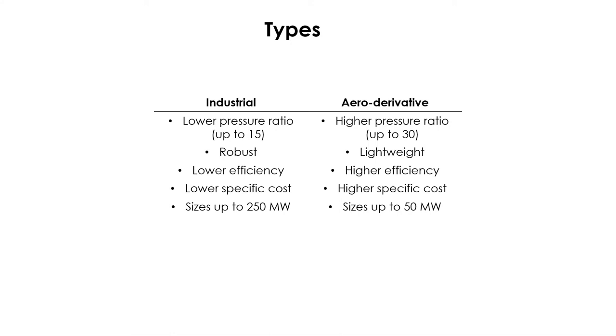This table compares the two types. Industrial turbines normally have a lower pressure ratio of up to 15. They are more robust, lower in efficiency, lower in specific cost, and the size is typically up to 250 MW.